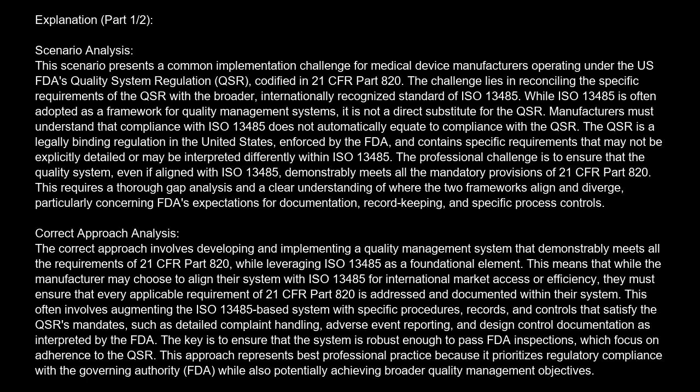The professional challenge is to ensure that the quality system, even if aligned with ISO 13485, demonstrably meets all the mandatory provisions of 21 CFR Part 820. This requires a thorough gap analysis and a clear understanding of where the two frameworks align and diverge, particularly concerning FDA's expectations for documentation, record-keeping, and specific process controls.